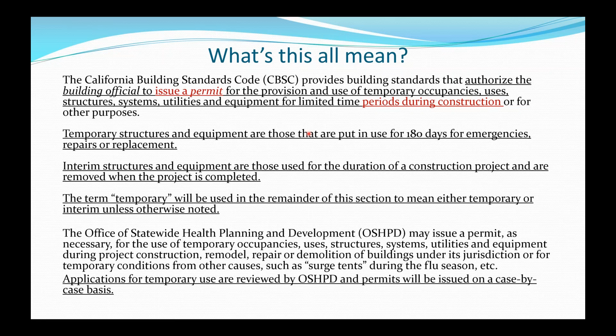OSHPD may issue a permit as necessary for the use of temporary occupancies, uses, structures, systems, utilities, and equipment during project construction, remodel, repair, demolition of buildings under its jurisdiction for temporary conditions or for other causes, such as surge tents during flu season. Applications for temporary use are reviewed by OSHPD and permits will be issued on a case-by-case basis. So if you're putting any temporary equipment or structures on site, it will need a permit.